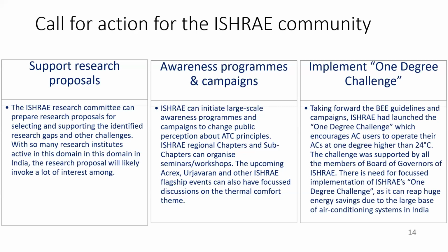So let me provide some background to this. The Bureau of Energy Efficiency has taken many steps to spread the message of energy savings through raising the AC set point temperature. It has mandated the default temperature setting of all ACs in the star labeling program at 24 degrees C. BEE has also issued voluntary guidelines to all commercial building consumers to maintain the temperature set point between 24 to 25 degrees C.